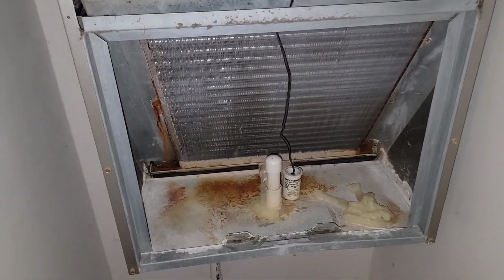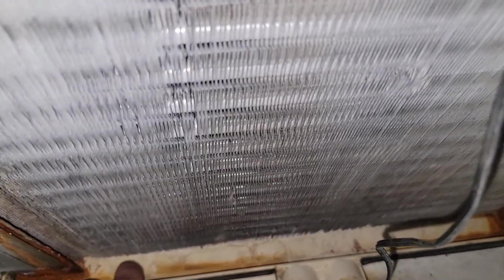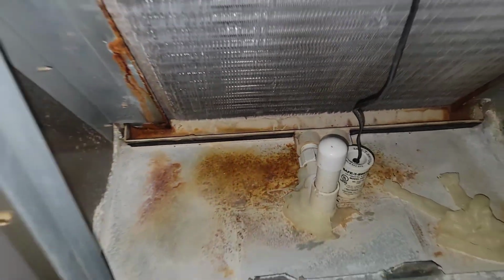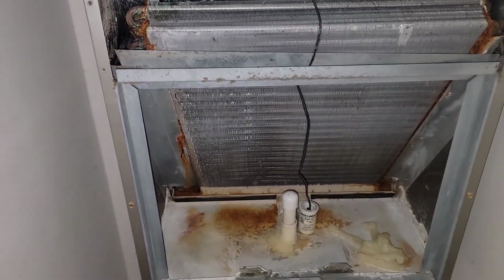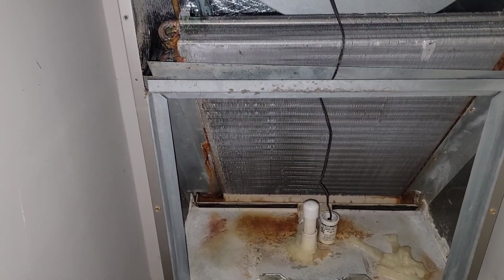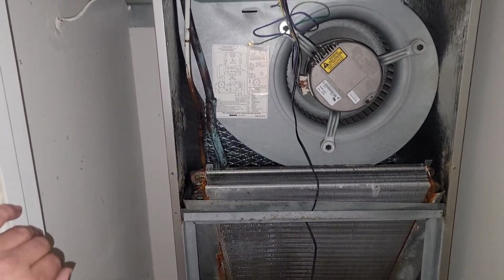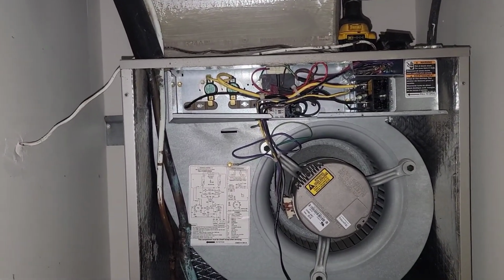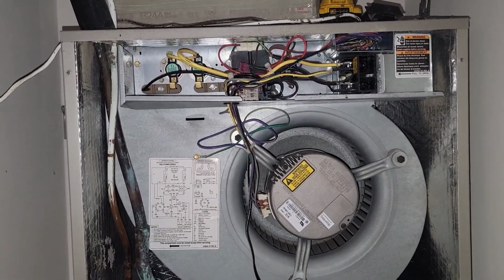So I'm pretty sure, I bet you this indoor coil is our problem. Of course, there's no water because it's been in the heat mode. But I bet you there'd be oil in here if there was water. I think I'm gonna get my leak detector out, do a little once over and check it. I already checked the condensing section. We don't have any issues.